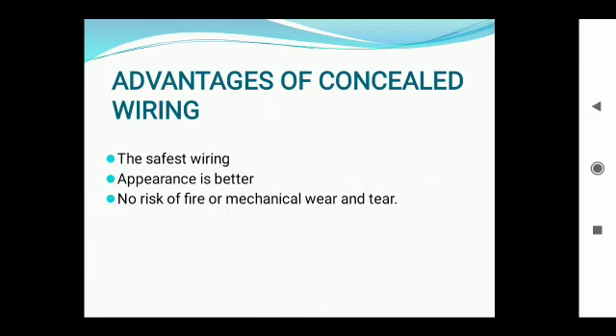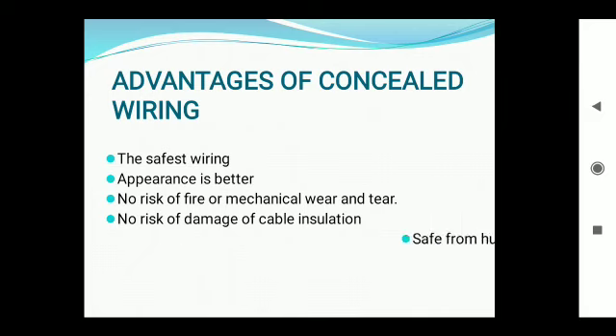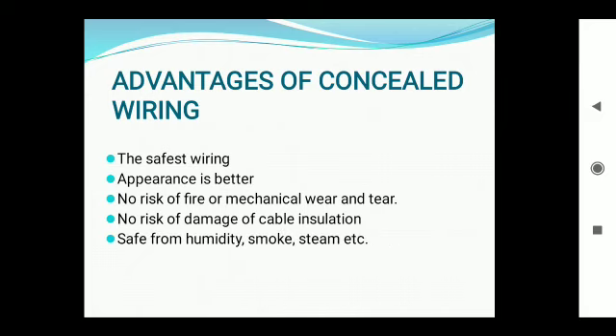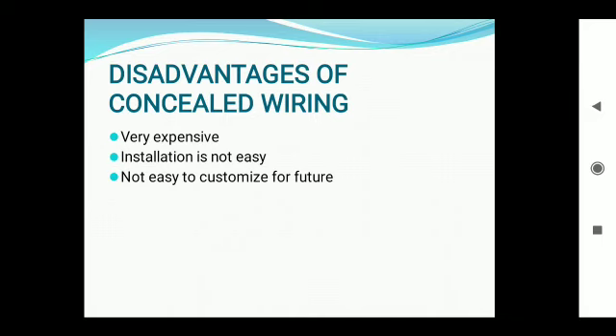The advantages of concealed wiring are the same as the advantages of conduit wiring. It is the safest wiring. Appearance is better. No risk of fire or mechanical wear and tear because it's an enclosed wiring. No risk of damage of cable insulation. Safe from humidity, smoke, steam, etc. No risk of shocks and long lasting. Now the disadvantages of concealed wiring. This is very expensive. Installation is not easy. Not easy to customize for future. Hard to detect the faults because it is installed under the wall.